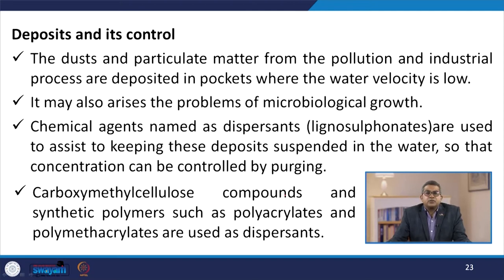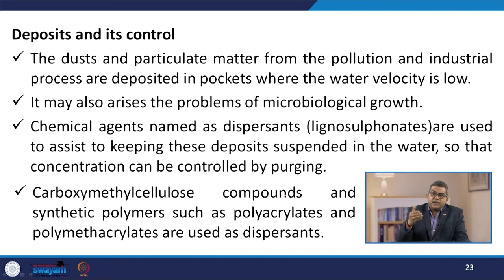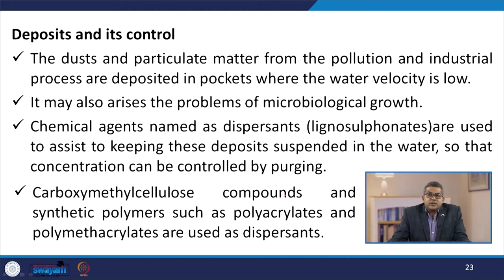Let us talk about deposits and their control. Sometimes dust and debris create problems for the effective operation of the cooling tower. Dust and particulate matter from pollution and industrial processes get deposited in pockets where water velocity is very low. This may also cause microbiological growth, which can further hamper the efficiency of the cooling tower. The chemical agents named dispersants, sometimes referred to as lignosulphonates, are used to keep these deposits suspended in the water so that the concentration can be controlled by purging.